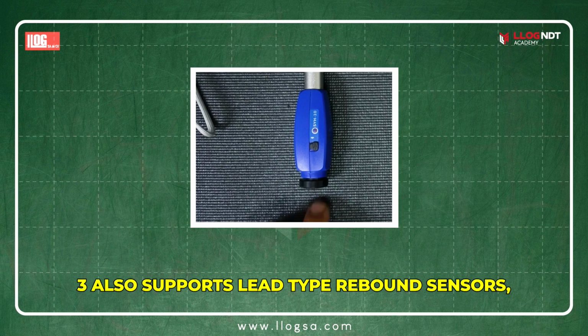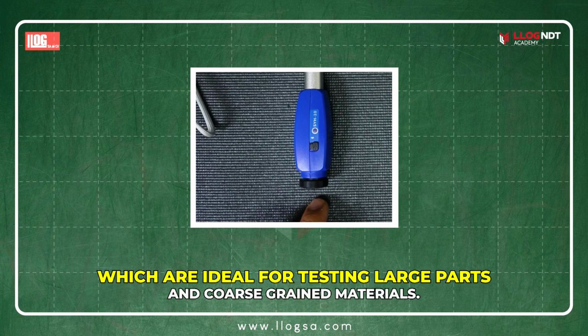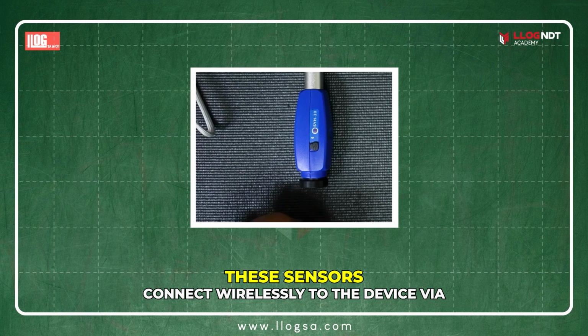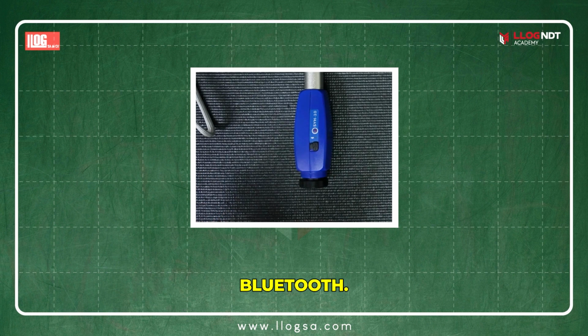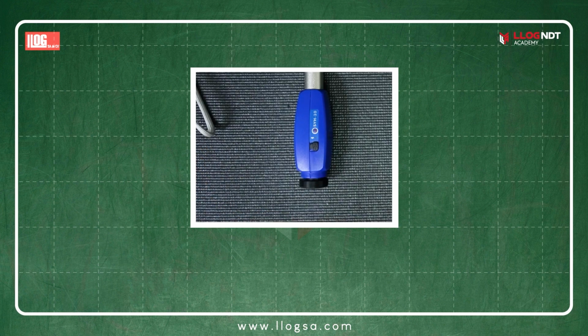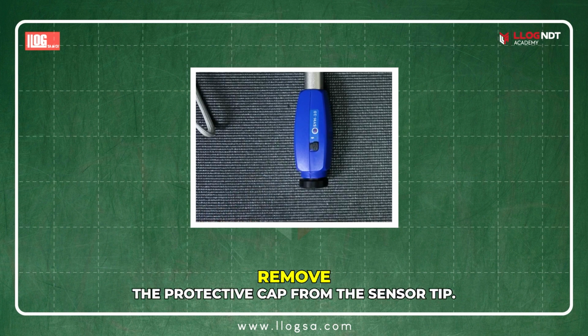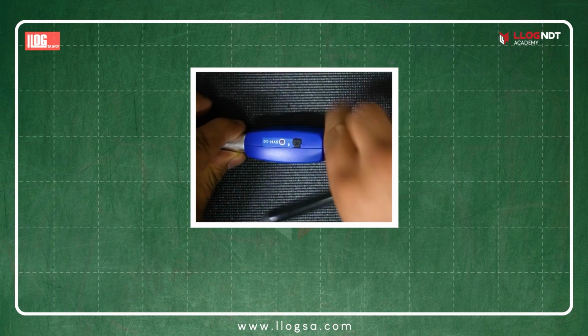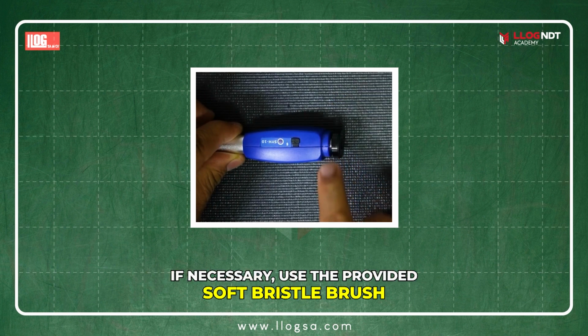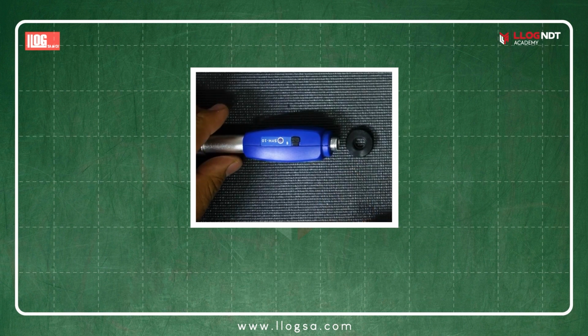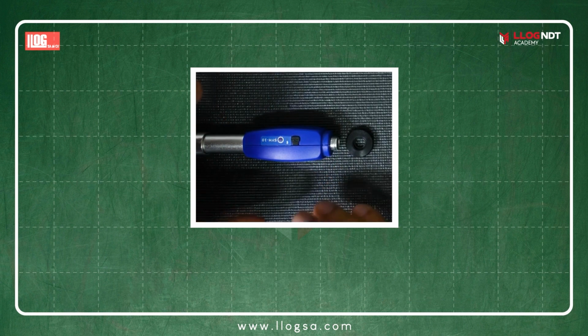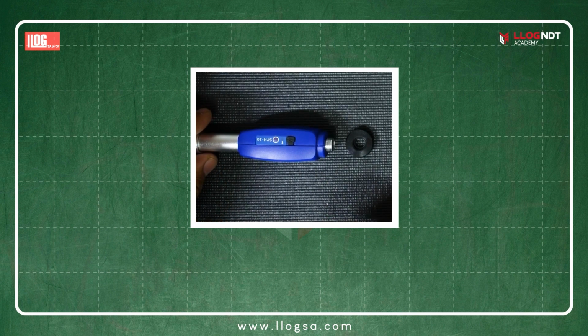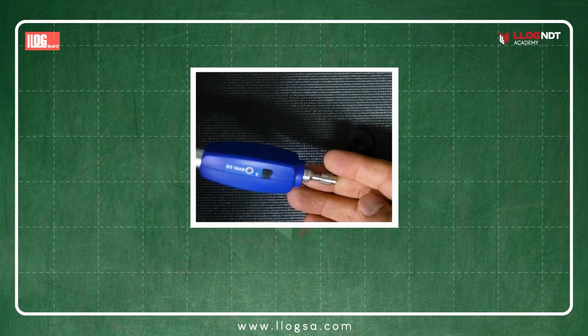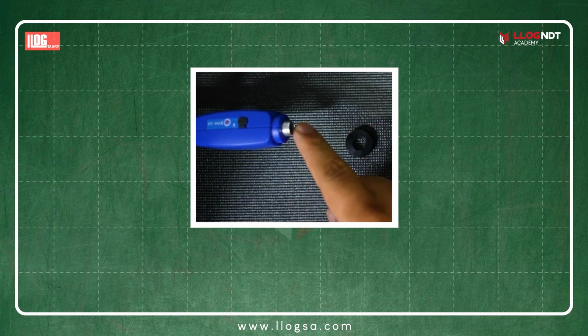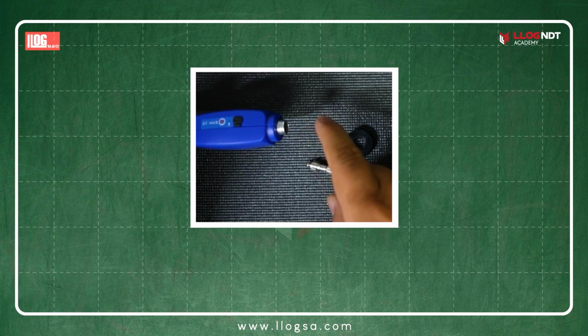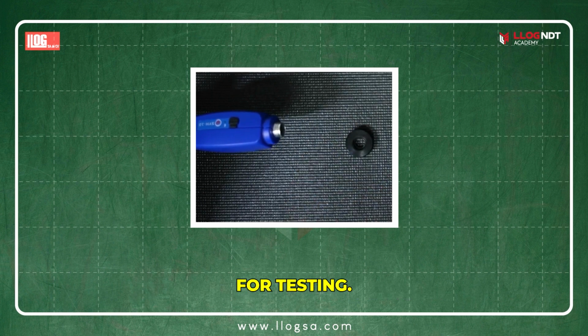The Sonodur 3 also supports lead-type rebound sensors, which are ideal for testing large parts and coarse-grained materials. These sensors connect wirelessly to the device via Bluetooth. To begin, remove the protective cap from the sensor tip. If necessary, use the provided soft bristle brush to gently clean the impact body inside the sensor. Reassemble the sensor and leave the cap off for testing.